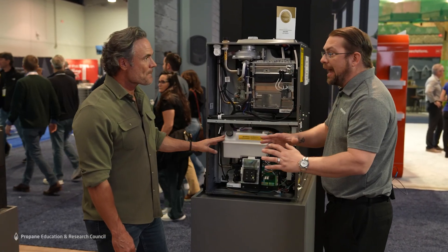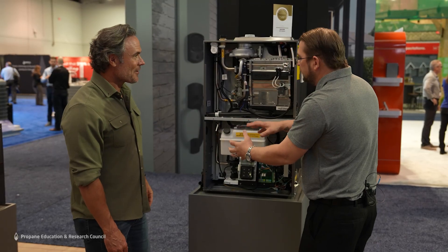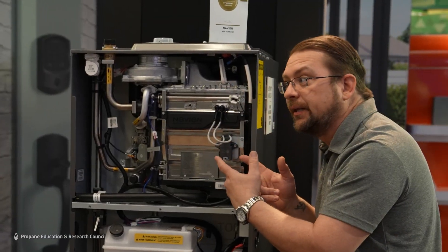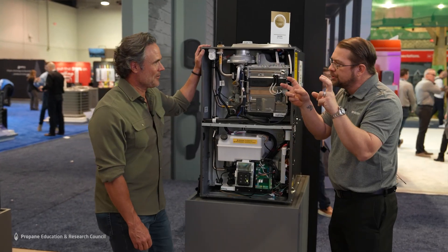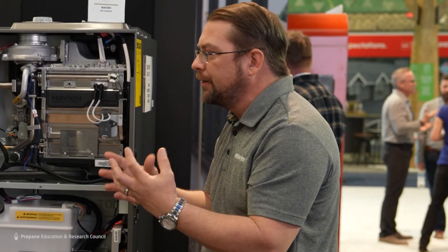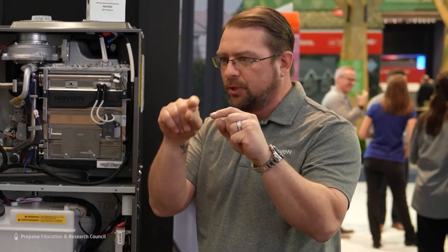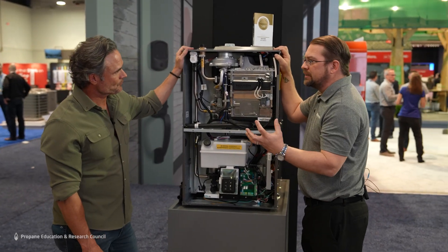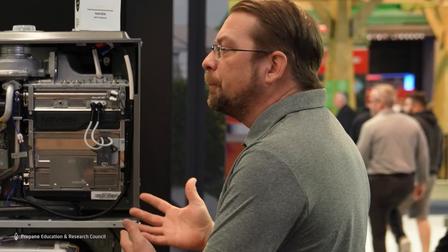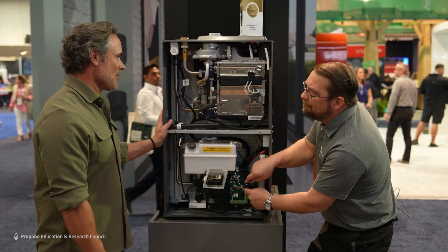You fill this up with tap water. That water is then pumped into a stainless steel heat exchanger on the outside, which heats the water. That water then goes through the hydronic coil. The ECM blower motor is full-featured and variable speed — not just the standard five speeds — and variable speed is what you want. From a serviceability standpoint, it's easy, and we know with competitors that serviceability has been a hurdle from a technician standpoint.